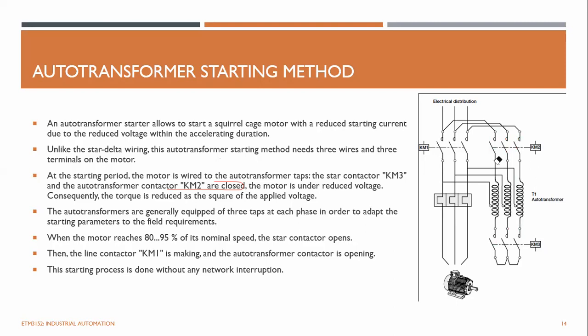And once the motor reaches full load, what you can do is just open them. The auto transformer is generally equipped with 3 taps per phase to adapt the starting parameters to field requirements. And when the motor reaches 80 to 90% of nominal speed, the star contactor opens, and then the line contactor KM1 makes the auto transformer contacts open. And this starting process is done without any interruption.